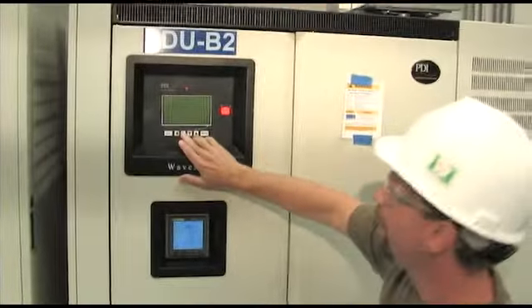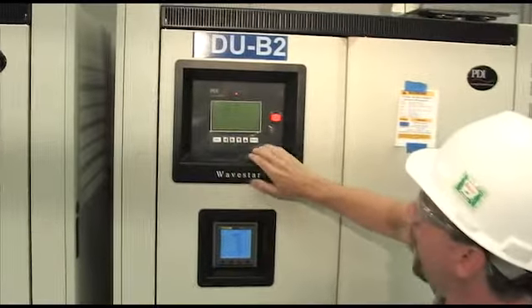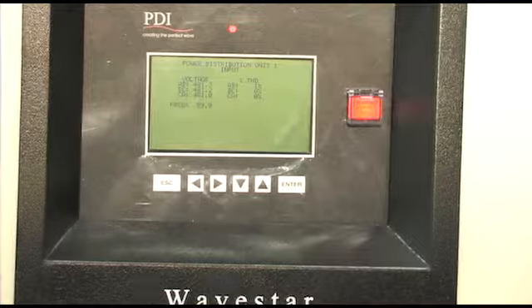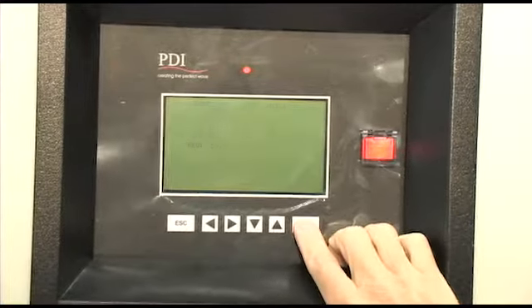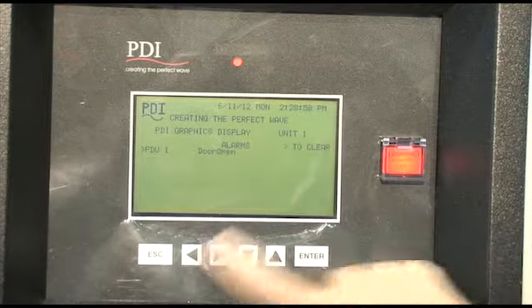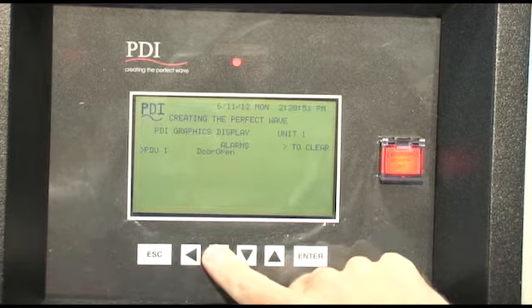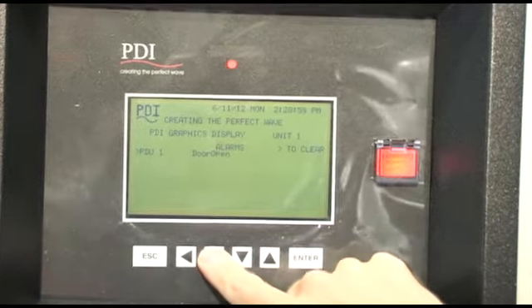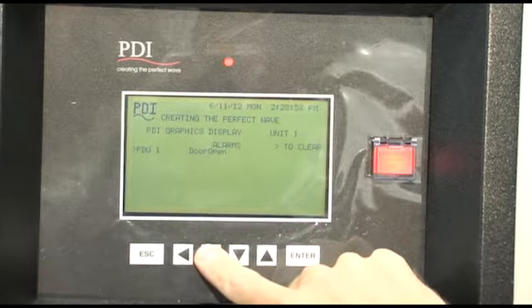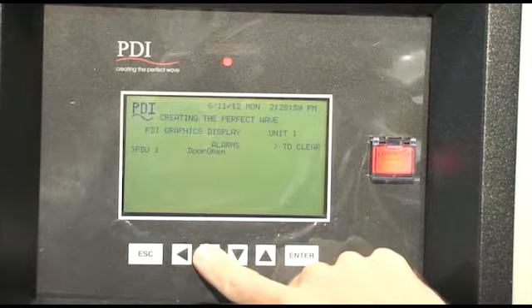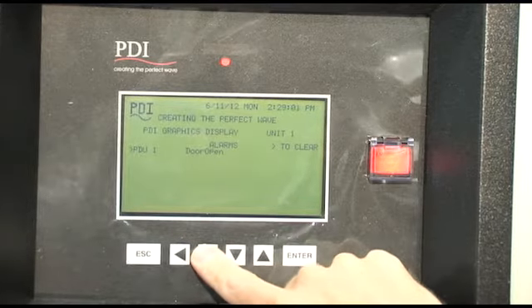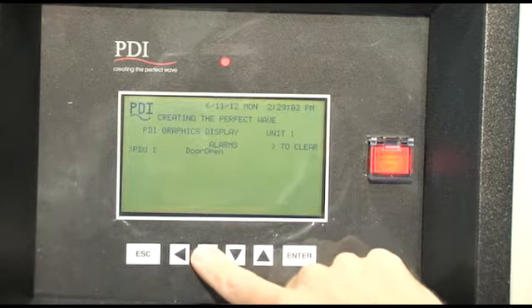Right here we have on the display basically a very simple display. And right now we have an LED at the top which is showing red. What I'm going to do is press enter to go to the alarm screen, and it has a door open alarm that needs to be cleared. You press the right arrow button to clear, and sometimes you have to press it for a little while, let go, press, but at some point it will turn green. And with that LED, if the LED is green, obviously things are okay.